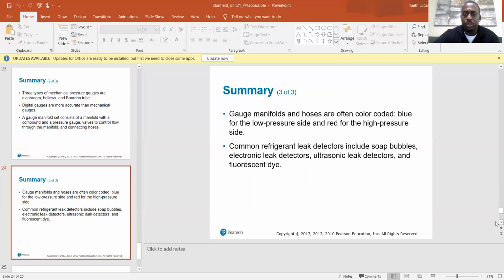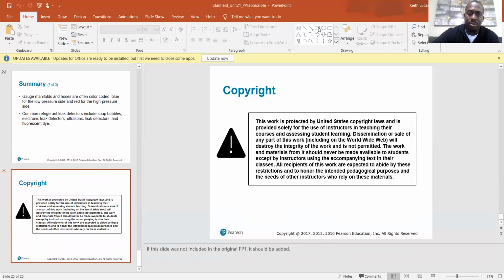Gauge manifolds and hoses are often color-coded, blue for the low pressure side and red for the high pressure side. Common refrigerant leak detectors include soap bubbles, electronic leak detectors, ultrasonic leak detectors, and fluorescent dye. The fluorescent dye is not one I use very often. I think they're making them better now, but they used to clog up TXVs on certain units, so it was something I was always advised against, so I haven't really used it a lot. I've used it once, and it worked, but again, it was just something I've always been kind of leery about doing. But anyway, so that's it for chapter 21.